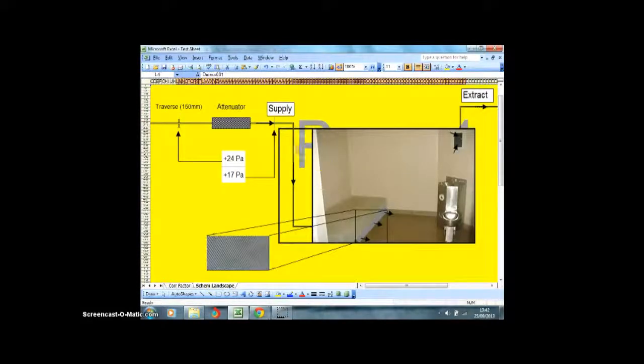Alright, I'll show the layout of a project that I've previously worked on. It's a holding cell down in Surrey, and on this layout, the typical layout for each one of these cells was basically 150mm duct through an attenuator which disappeared down an enclosure into the cell. Fresh air was supplied from the perforated slot underneath the bed, and extract air just over the lavatory, but we're not going to concern ourselves with that for the time being, as the main focus for this exercise is just on the supply itself.